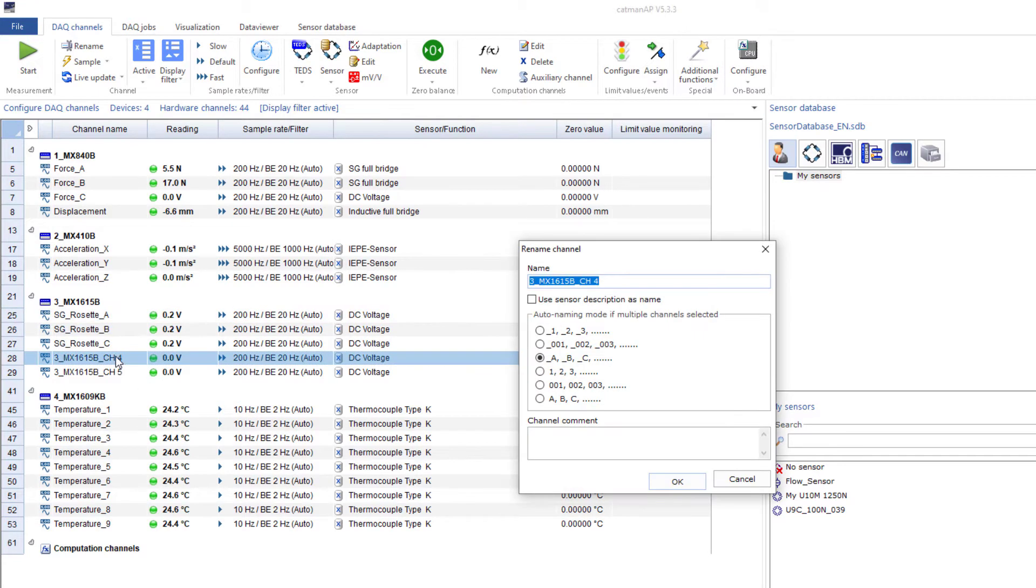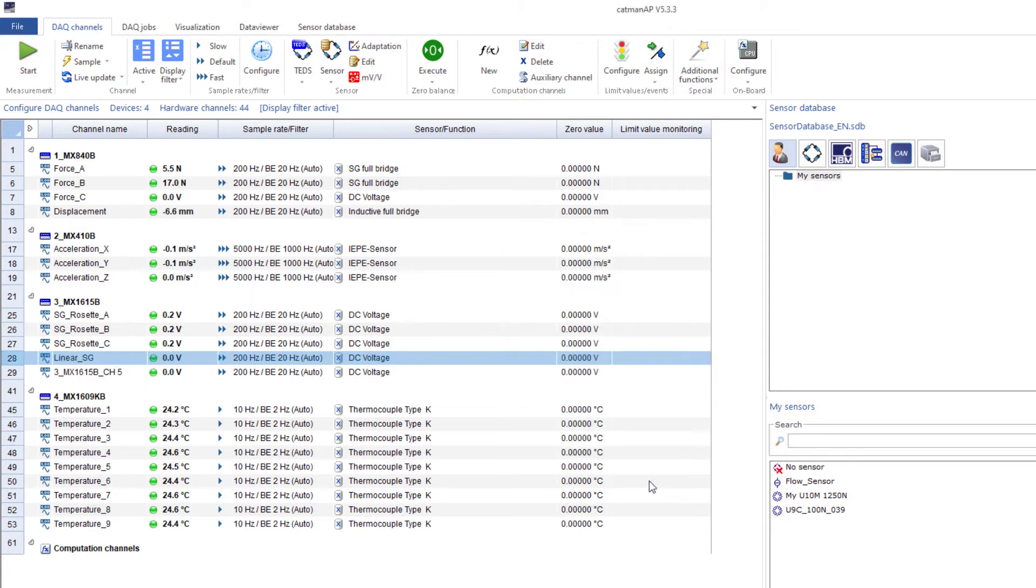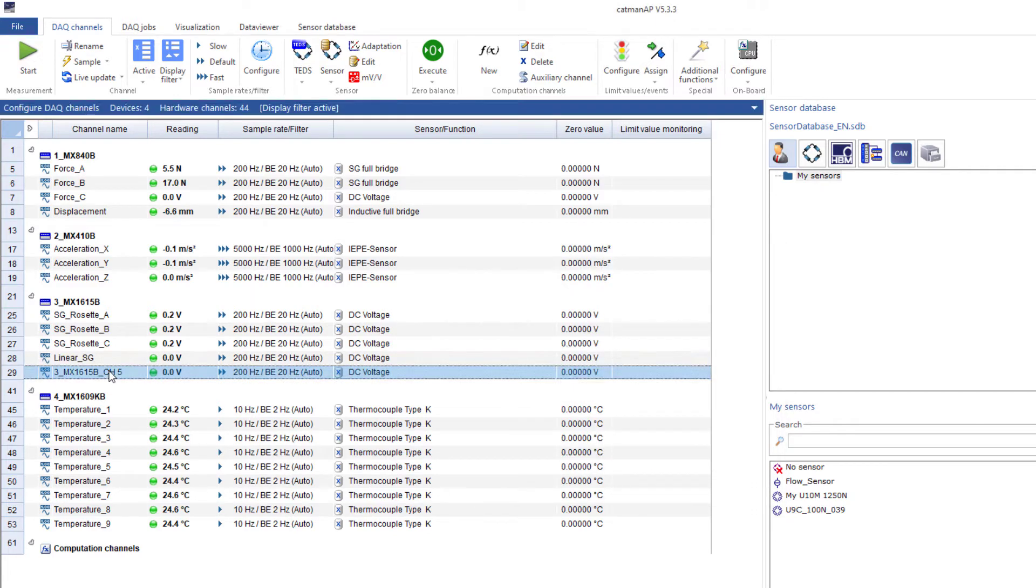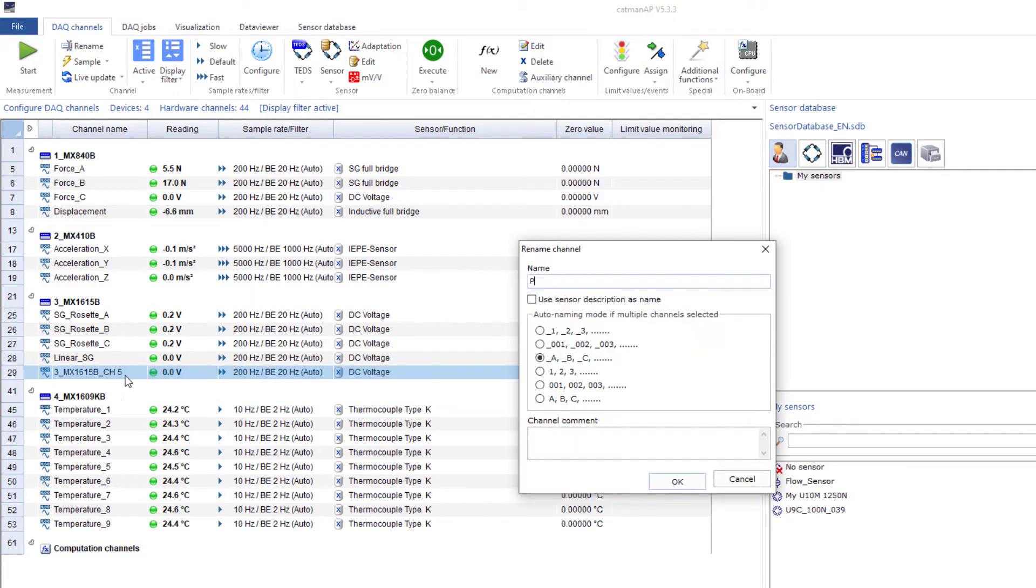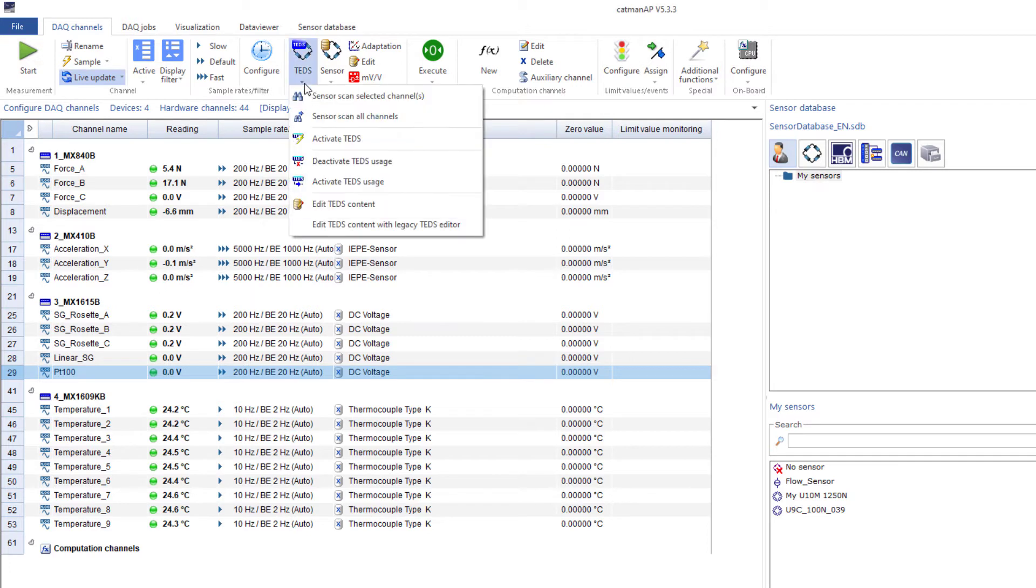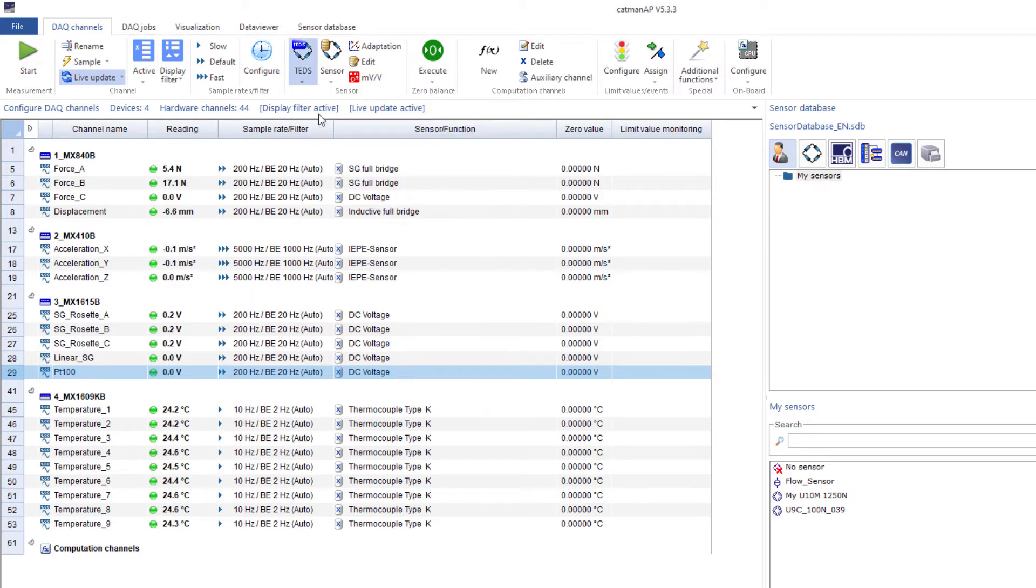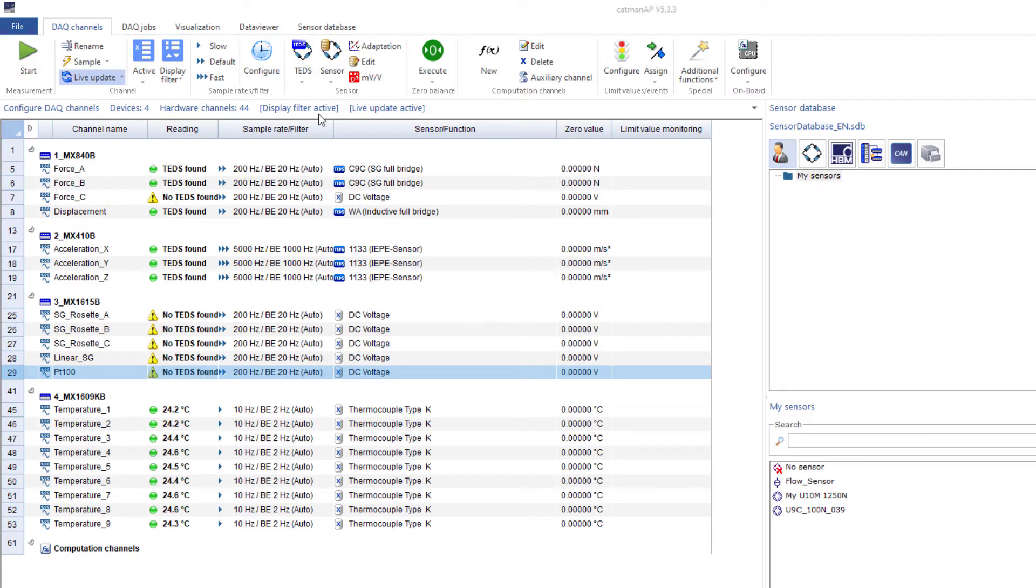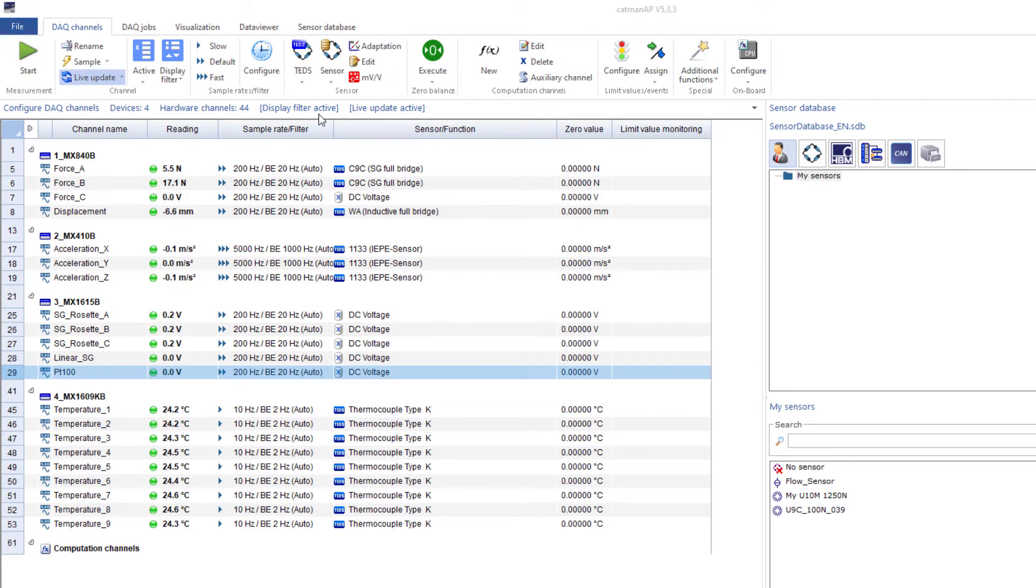I'll name the linear strain gauge Linear Strain Gauge, and finally the PT100 for temperature compensation. Now, I'll search across all channels for sensors with TEDS. This completes the sensor configuration for these channels. Then, I'll use the sensor definitions from the sensor database to configure the channels to which no sensor with TEDs chip is connected.